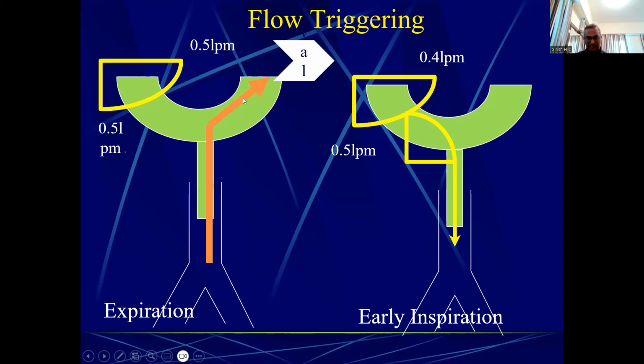Patient is exhaling. And when they have flow triggering, what these ventilators have is something called a bias flow. Bias flow is not the main flow, which comes after the patient triggers the breath. That is the main flow of breath. But throughout the cycle, expiration and exhalation and inhalation, there is a constant flow across the inspiratory limb. Like for example, here 0.5 liter is going in and 0.5 liter is coming out, right? Because the patient is exhaling, this 0.5 liter goes through this and goes out. So it is constantly being monitored here.